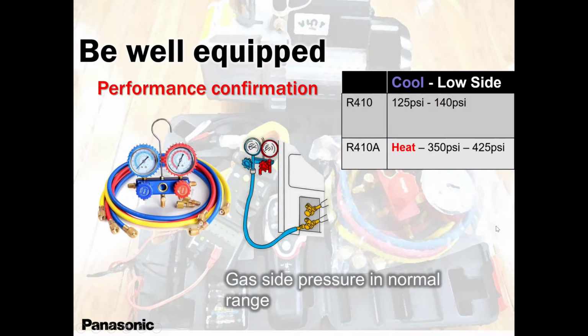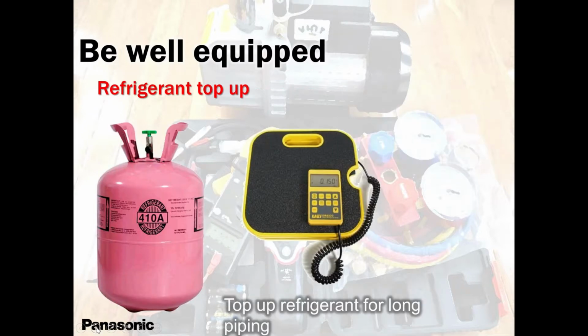Once again, these are your pressures: 125 to 140 in cooling, 350 to 425 in heating. Okay, when it's running at 350, it's probably still on lower amps, probably 3-4 amps on a 15,000 or a 12,000 BTU unit. And when it gets to 425, we are talking about full running amps, 6.8, 7 amps on same 15 or 12,000 BTU, and a little bit higher in amps with 18,000 and 24,000 BTU.